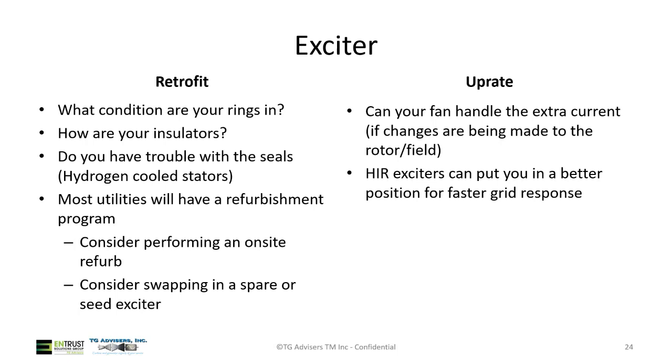For the uprate, can your fan handle it? There's going to be extra current potentially on your rotor field. And then the last thing for exciters I want to mention is that HIR exciters are not new, but they're being talked about again. They were new in the 70s, I believe. But they're being talked about again because of the increased demand for fast response.